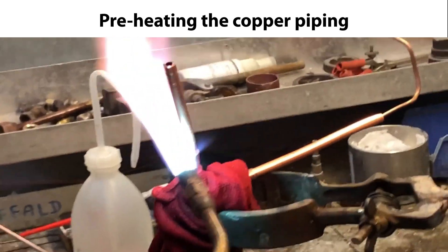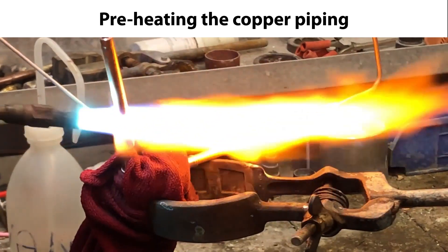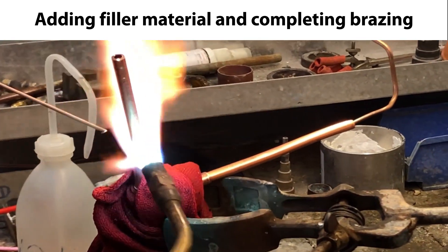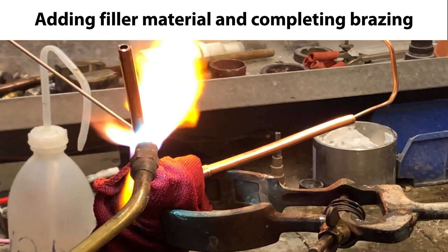The first step is to carefully preheat the piping to ensure that the brazing filler material being used will melt correctly and make a tight connection. For this small valve with small connections this only takes a few seconds as seen here. Then carefully add the brazing filler material to the connection between valve and piping while still heating the connection, and complete the brazing as seen here.